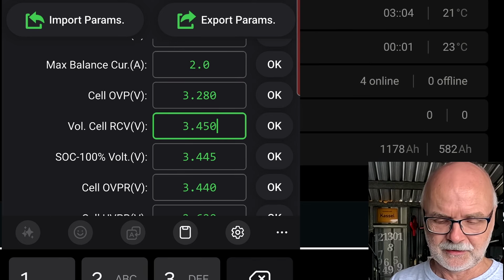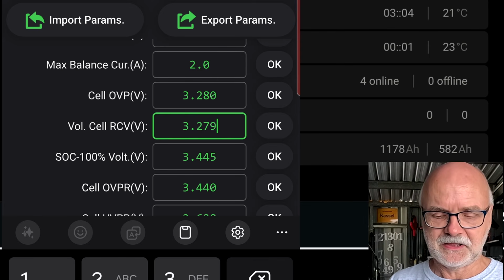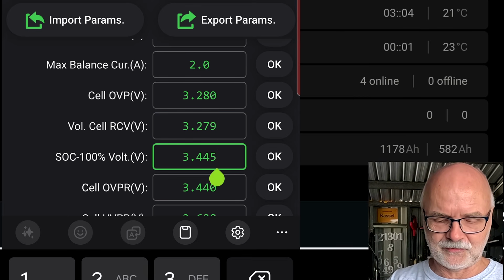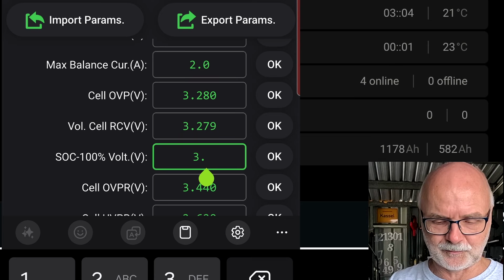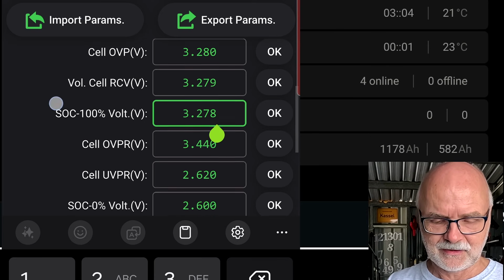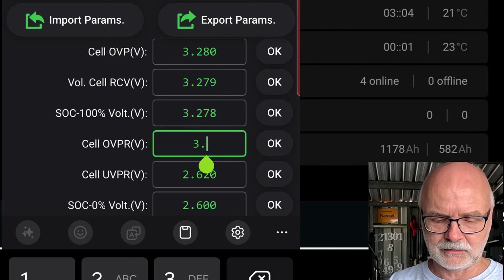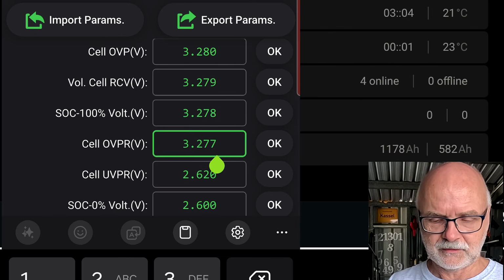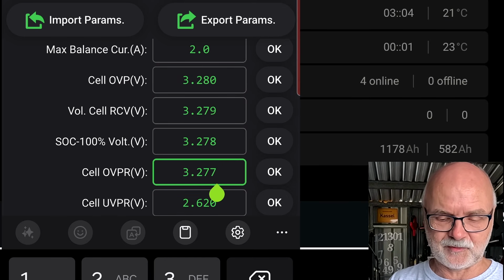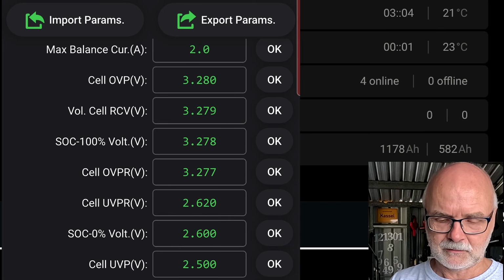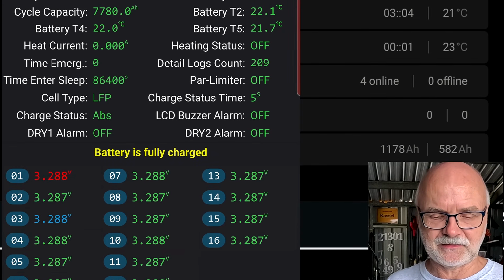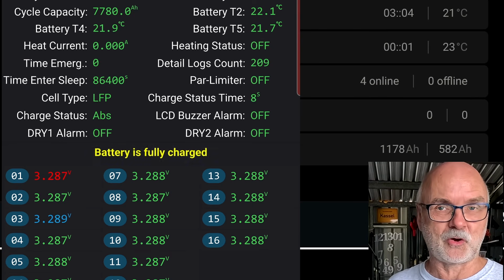The cell requested charge voltage, for example, needs to be lower than the over voltage protection. So we can set this one to 279, for example, 1 millivolt lower than the over voltage protection. And the same for the state of charge 100% reset voltage, which needs to be lower than the RCV. So 278. And then the recovery needs to be even lower, so 277. That's it. Now we've got them in the correct order and we can start from the bottom to accept them. You say okay, okay, okay, okay. So now we should see an alarm after a couple of seconds. Battery is fully charged because we have reached the 3.28 volts. And you can see up here the charge MOSFET has turned off.